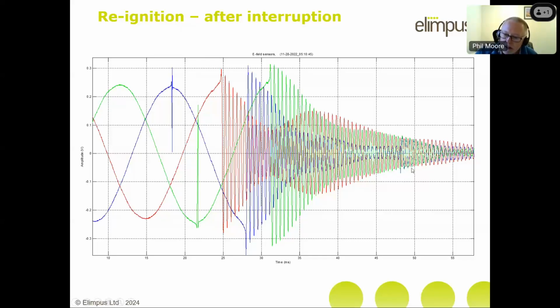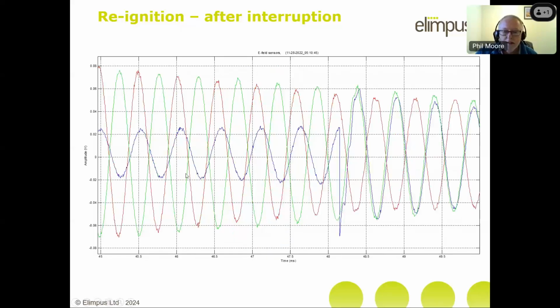But if you just look around about 48 milliseconds or so, you can see that there is something going on there. Let me just zoom in on that on the next slide. Okay, and you can see here is the blue phase reactor transient, and look at that. You can see now there's been a reignition there. Not for very long, just maybe a few microseconds or so, and then it's gone out again. But the fact that this has happened at 48 milliseconds after the breaker was instructed to open is extremely bad news, and we observed this over several operations, and we recommended that in fact the breaker was taken out of service.